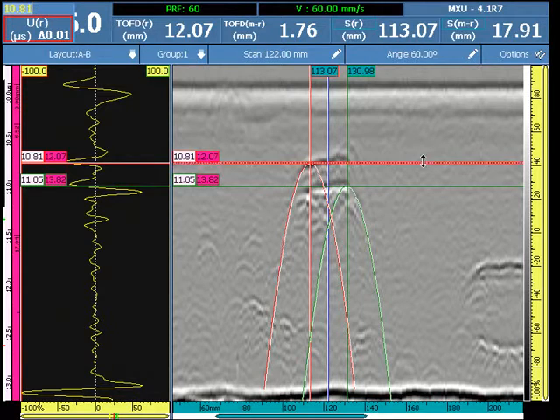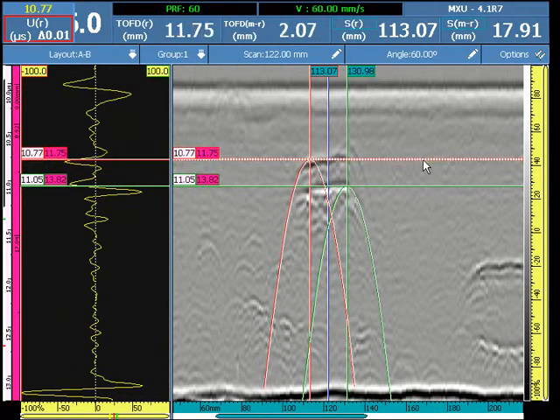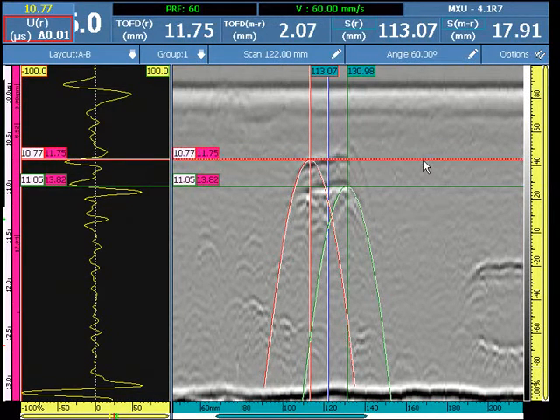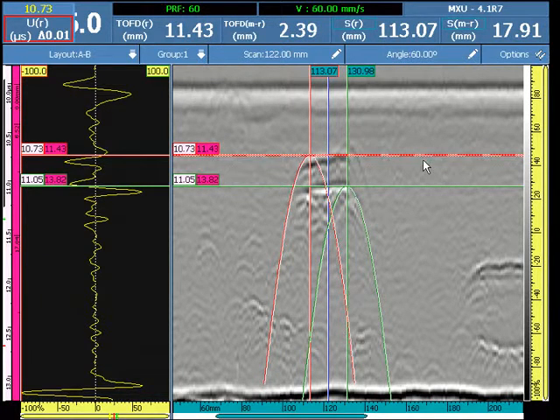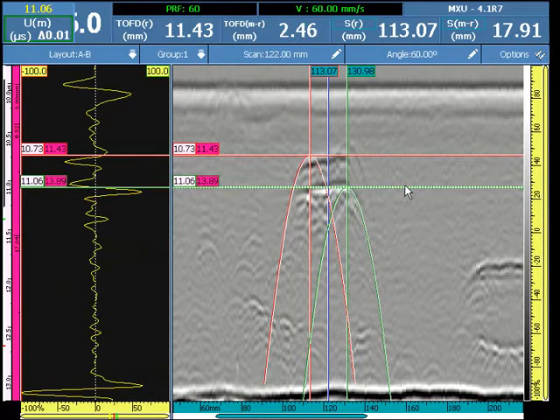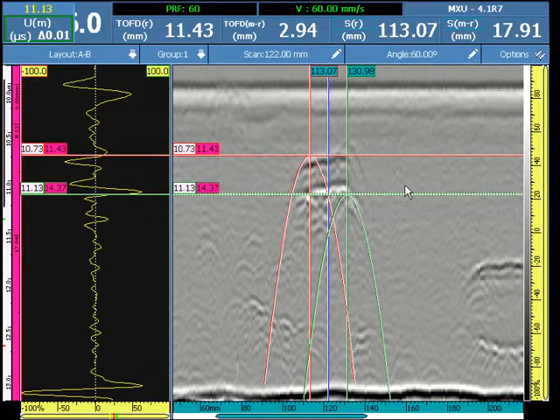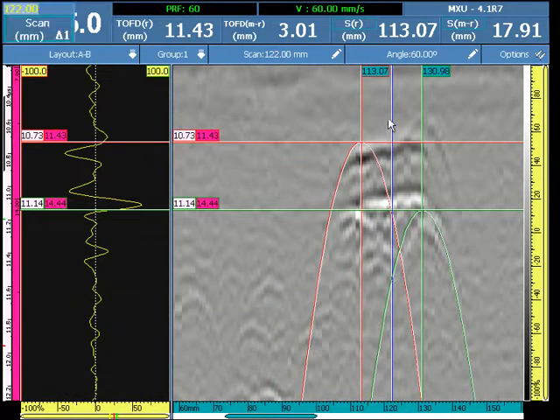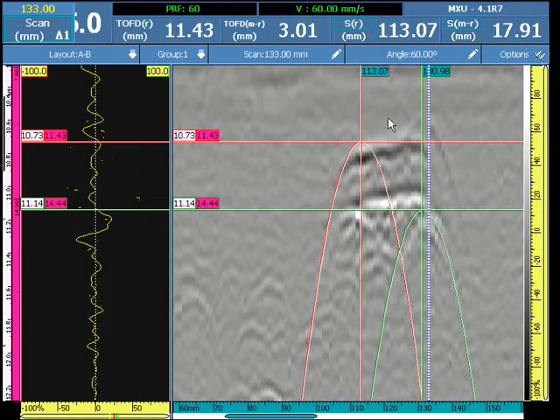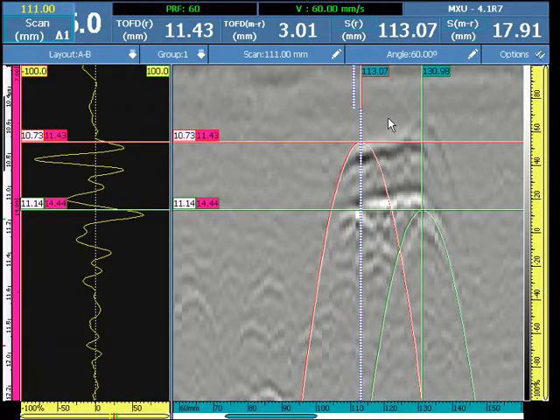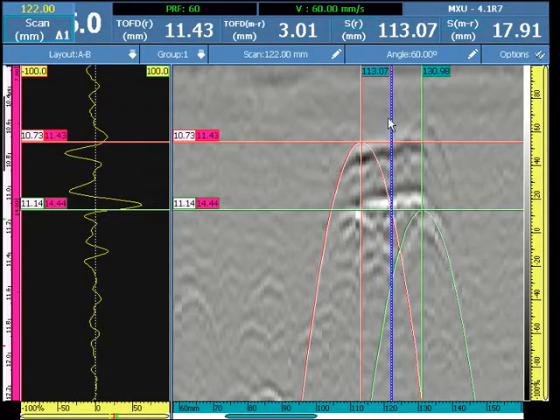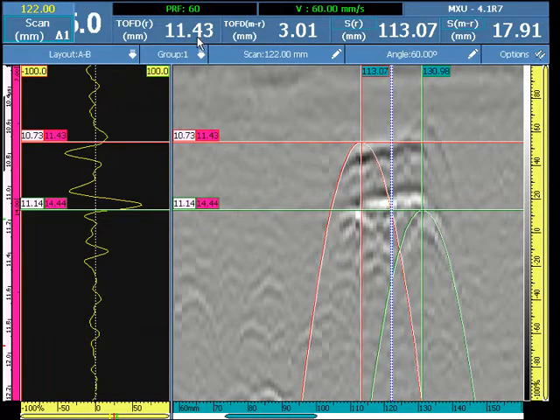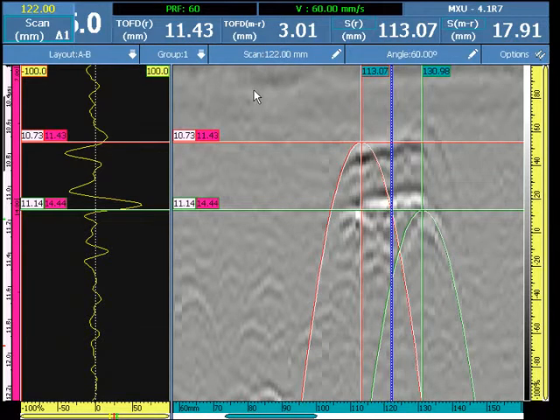Select the UT axis cursor to position it at the top of the flaw, and the measure cursor on the UT axis at the bottom of the flaw. We'll use our data cursor again to watch the A scan as we move in and out and left and right. When the cursors are positioned, we can see we have a flaw that starts at 11 millimeters and is 3 millimeters in height. It's directly in the middle of the weld of a double V weld, so we know this is an inadequate penetration. The length of the flaw is available here.